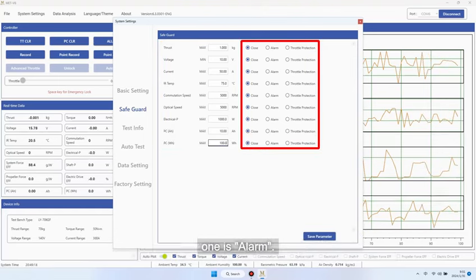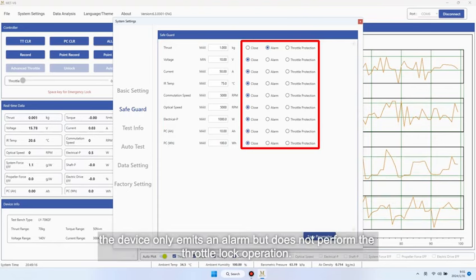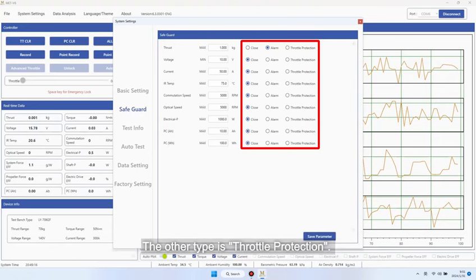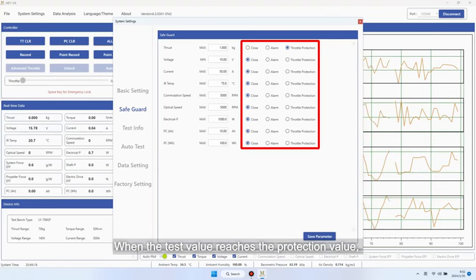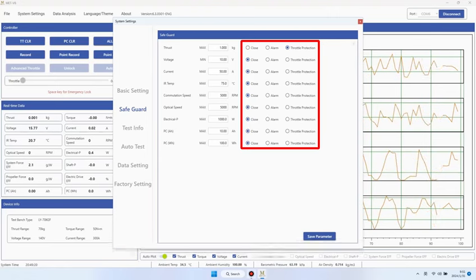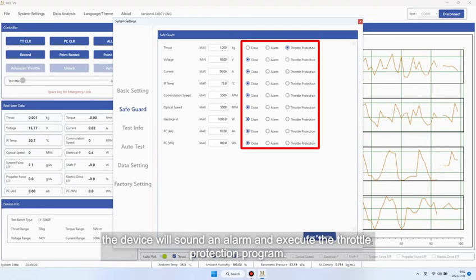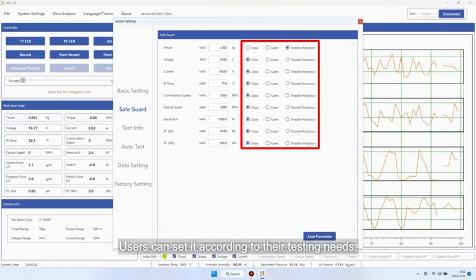There are two modes of safeguard. One is alarm. When the test value reaches the protection value, the device only emits an alarm but does not perform the throttle lock operation. The other type is throttle protection. When the test value reaches the protection value, the device will sound an alarm and execute the throttle protection program. Users can set it according to their testing needs.